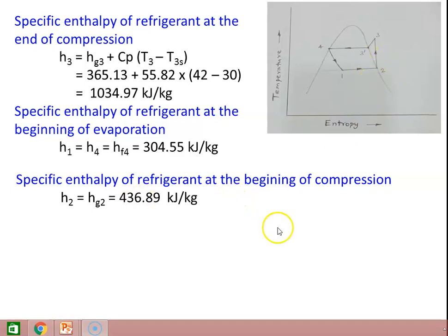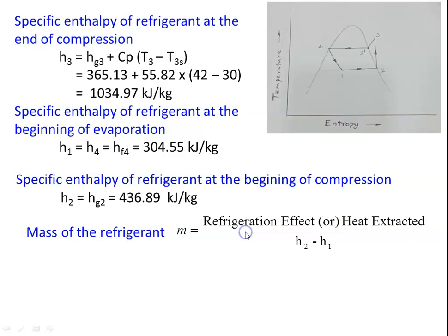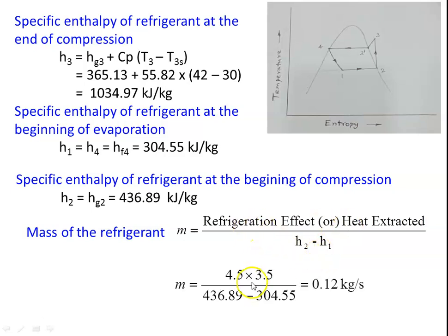Here point 2 is saturated vapor. The mass of the refrigerant M = refrigeration effect / (H2 - H1). The refrigeration effect is 4.5 tons, and 1 ton of refrigeration equals 3.5 kJ/s. So M = (4.5 × 3.5) / (436.89 - 304.55) = 0.12 kg/s. The mass of the refrigerant flowing through the circuit is 0.12 kg/s.